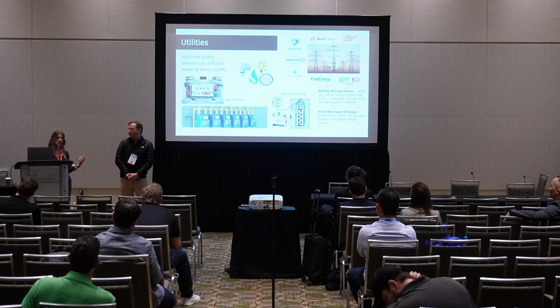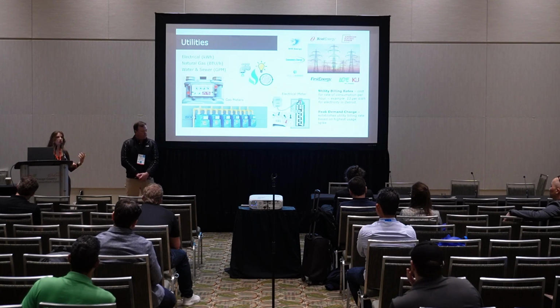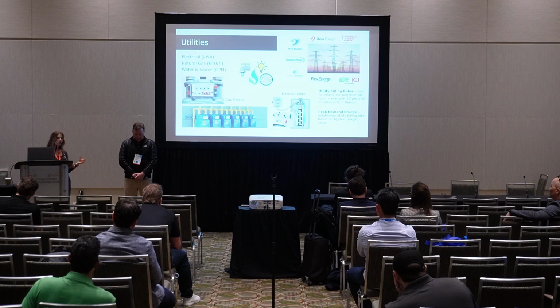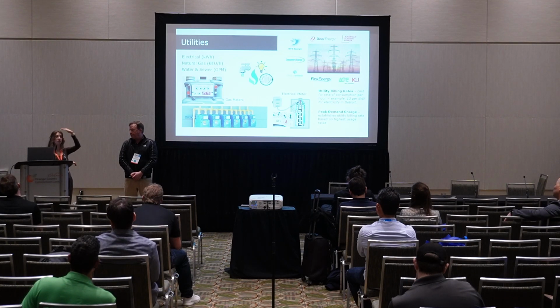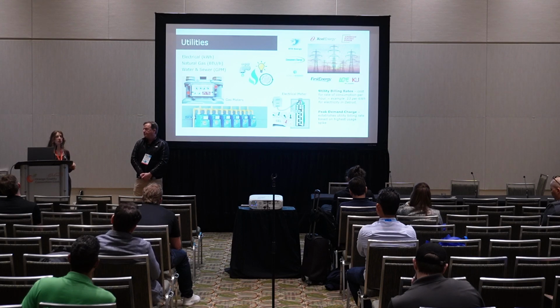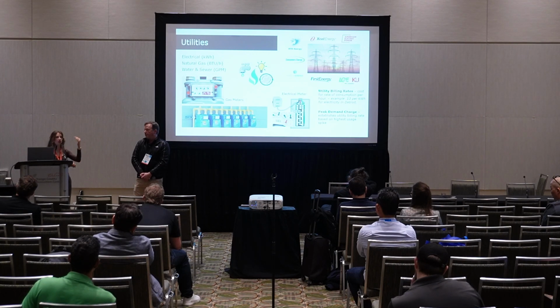That's why it's so important to watch these - we'll do a lot of what's called demand response. So it's like, okay, I know that in the summer my peak demand typically is in the afternoon when all my cooling systems are kicking on. You can do a demand response where, if you're starting to hit your thresholds, you have a lower threshold where you start doing things a little bit, and a higher one where you're really high and need to really drop things. You can do it based on a trigger point - if it reaches this point, do things. So maybe ramp the fans down to 75%, relax the set points a little bit, turn down the pumps, or turn off some spaces or lights.